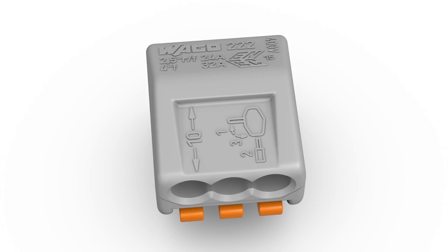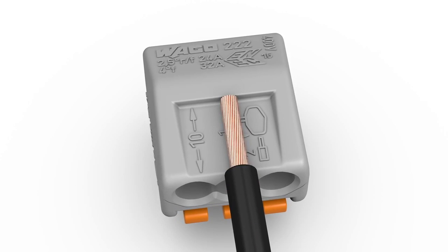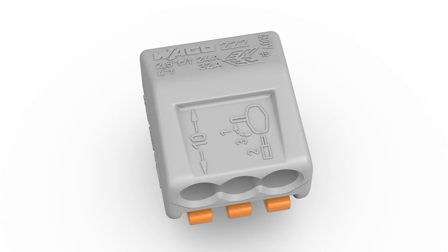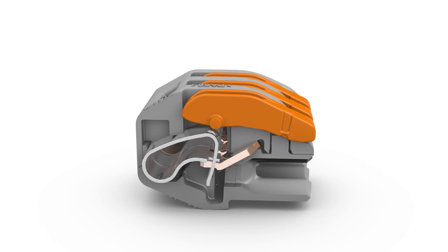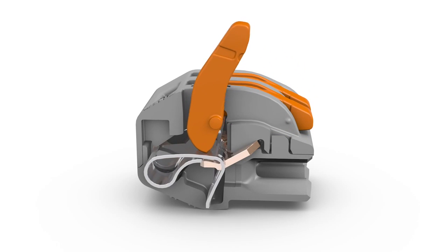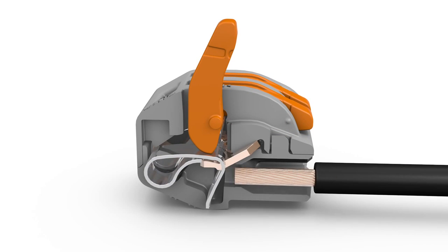Wiring is very easy. Strip the conductor to 9 to 10 millimeters or 0.37 inches, open the clamping unit via the integrated lever.